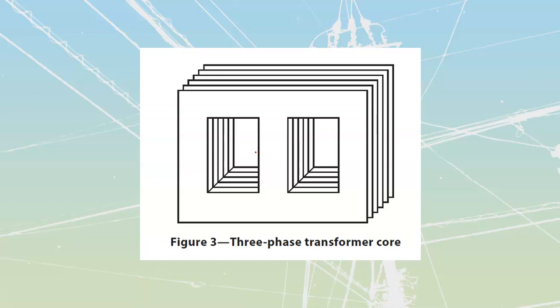At any given moment, all the flux is going to be equal. We always have what we refer to as balance inside here. So if I've got a large amount of flux over here, flux plus plus, it is going to be balanced out by a flux minus minus, or a flux in the opposite direction. It might be spread over two other legs, or all into a single leg. There are multiple different ways it gets distributed, all based upon exactly where we are inside that three-phase cycle.